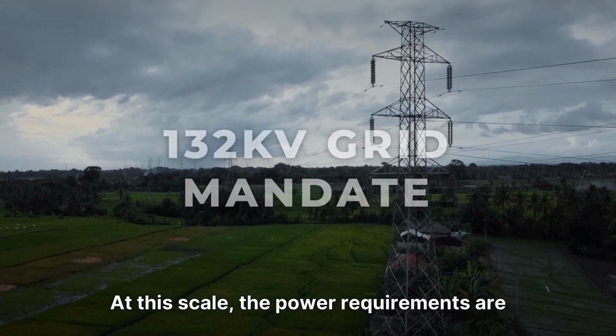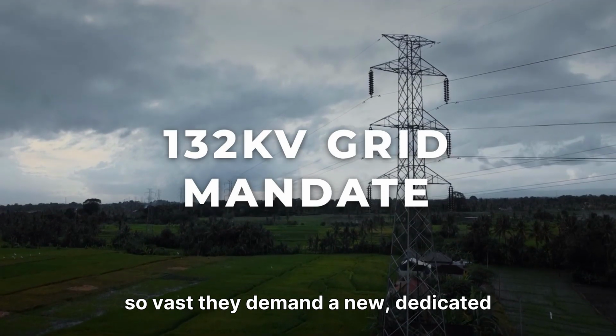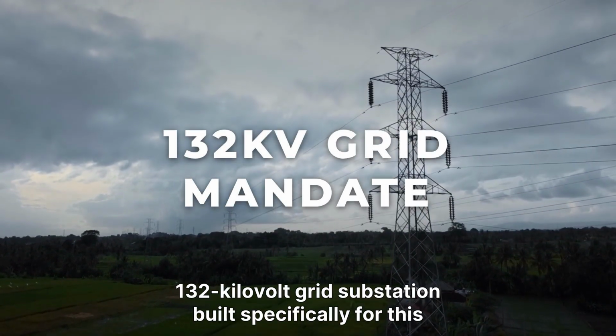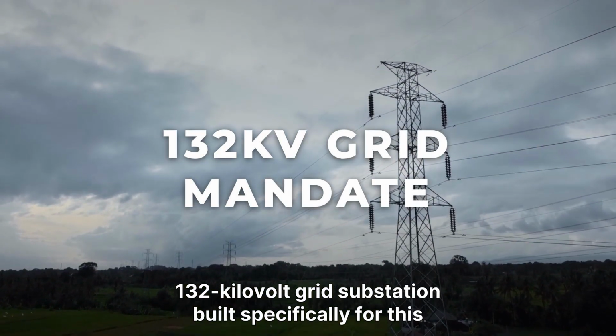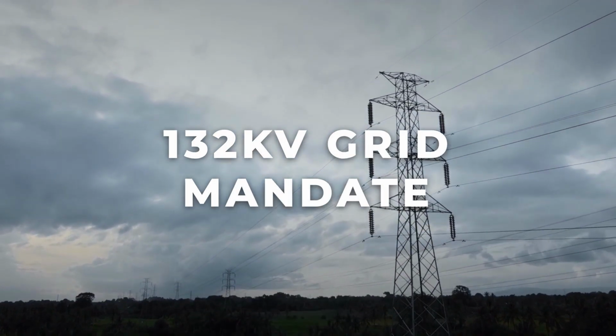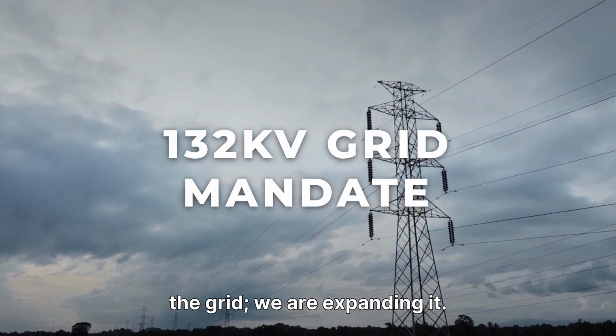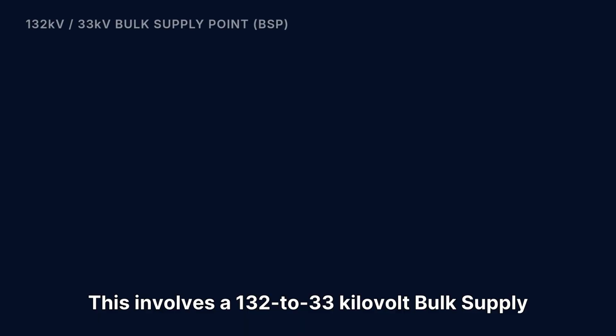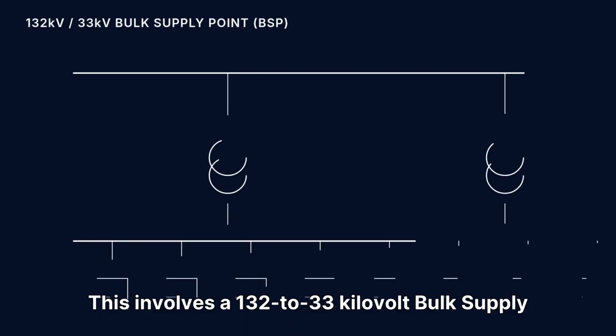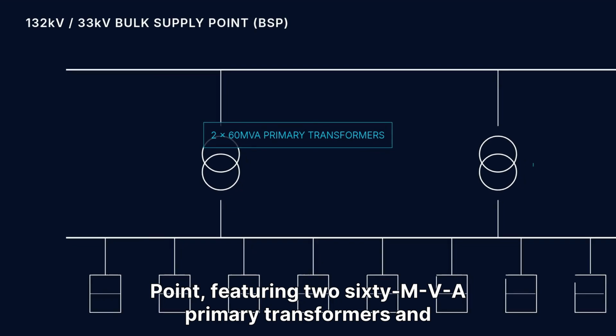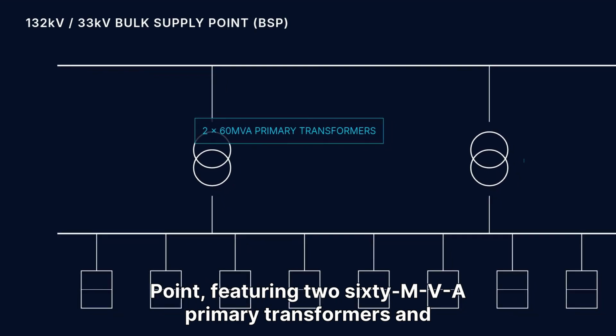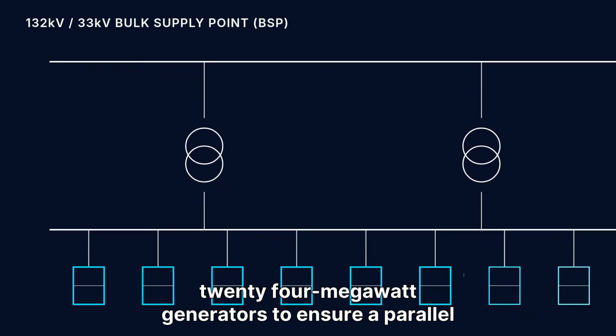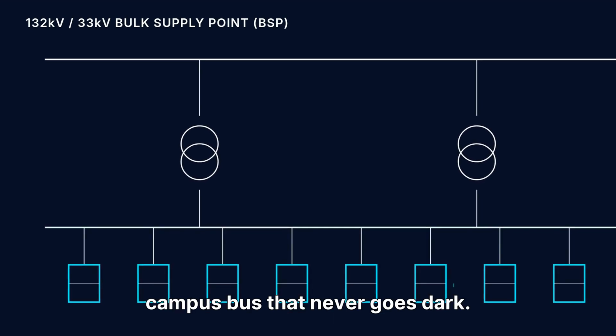At this scale, the power requirements are so vast, they demand a new, dedicated 132 kilovolt grid substation built specifically for this campus. We are no longer just connecting to the grid, we are expanding it. This involves a 132 to 33 kilovolt bulk supply point featuring 2 60 MVA primary transformers and 24 megawatt generators to ensure a parallel campus bus that never goes dark.